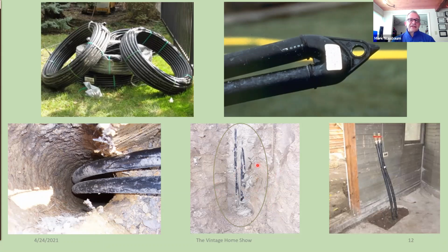Because the whole goal here is to move energy from this pipe into the ground and from the ground into the pipe. And so you need a good conductive material. The other thing the grout does is it's required by the state well drilling code to ensure the aquifer that we might drill through doesn't get contaminated with surface water or aquifers transferring between themselves or whatever. So it's just an environmental protection.